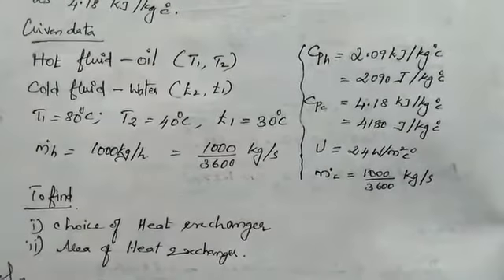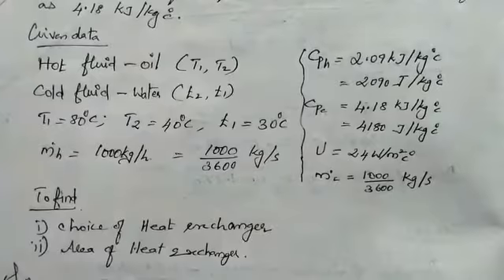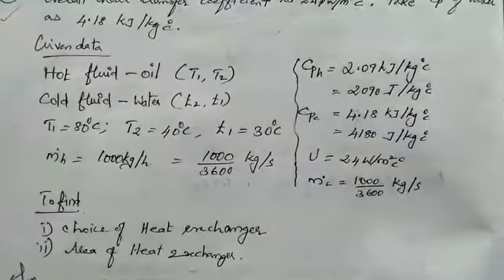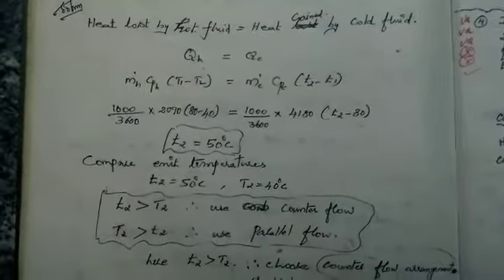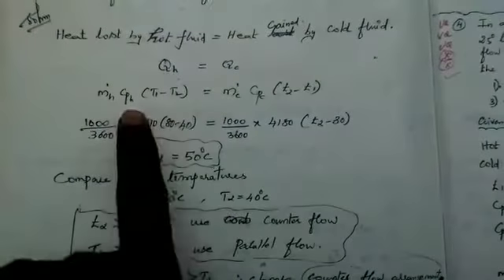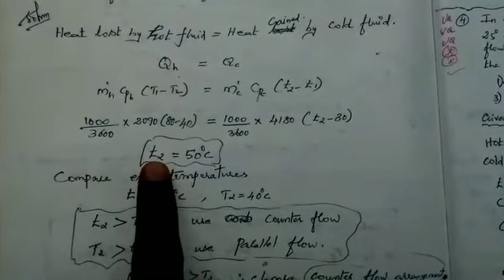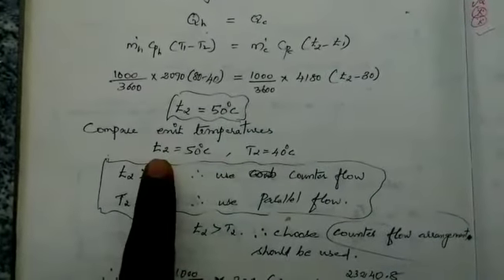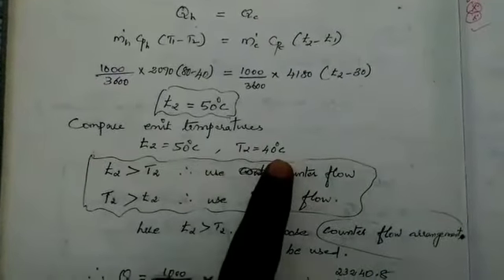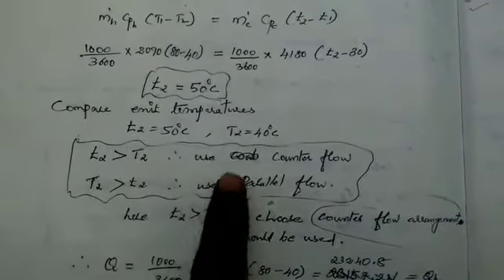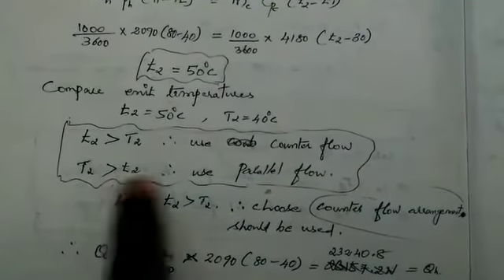Now we find the choice of the heat exchanger — parallel flow or counter flow — and calculate the area. Heat loss by hot fluid equals heat gain by cold fluid: QH = QC. Substituting, exit temperature of cold fluid t2 = 50 degree Celsius. Capital T2 = 40 degree Celsius. Since T2 is less than t2, we use counter flow.